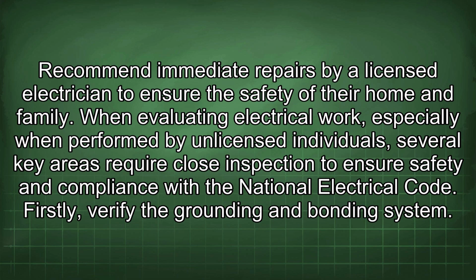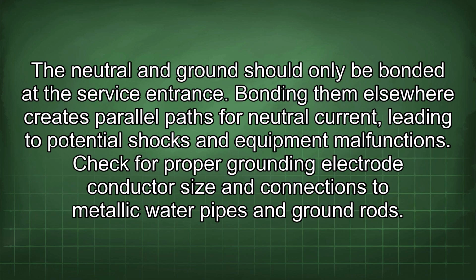When evaluating electrical work, especially when performed by unlicensed individuals, several key areas require close inspection to ensure safety and compliance with the National Electrical Code. Firstly, verify the grounding and bonding system. The neutral and ground should only be bonded at the service entrance. Bonding them elsewhere creates parallel paths for neutral current, leading to potential shocks and equipment malfunctions. Check for proper grounding electrode conductor size and connections to metallic water pipes and ground rods.